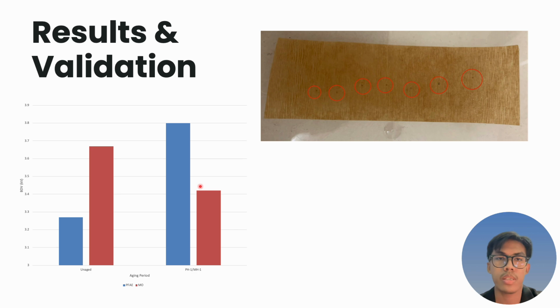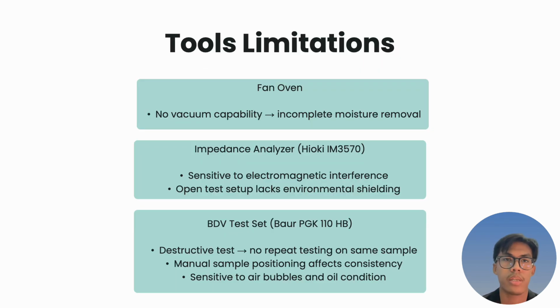So BDV results support this observation, with PH1 achieving 3.80 kV, while MH1 dropped to 3.42 kV, confirming that PFAE offers better thermal resilience. So this image shows the puncture hole after breakdown occurred. So these findings are validated against literature that reports ester oils offer higher fire points and environmental benefits but are more sensitive to moisture. So tools limitation.